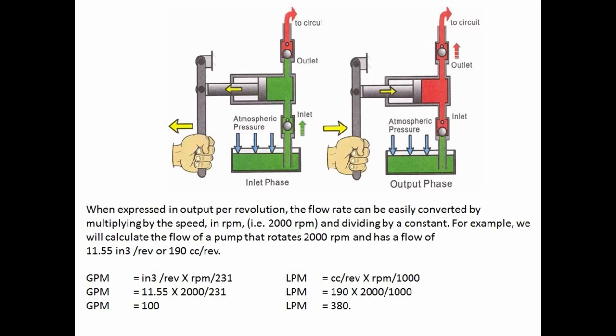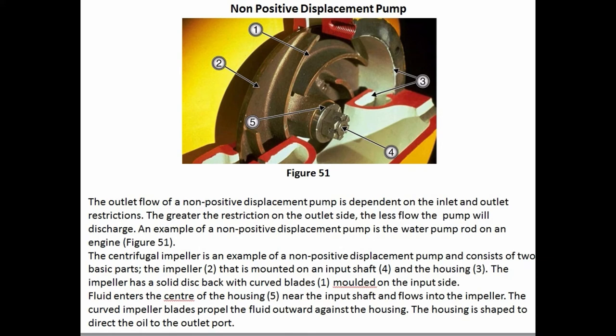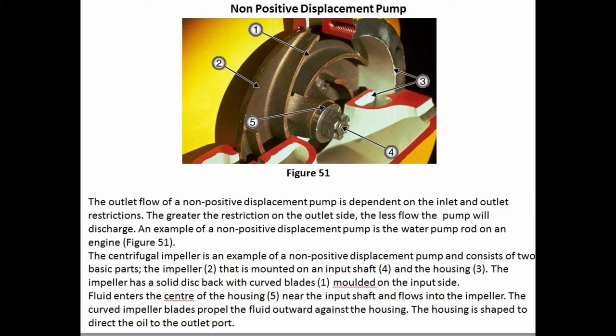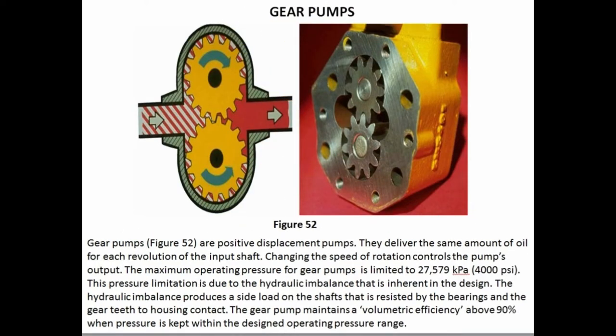The outlet flow of a non-positive displacement pump is dependent on inlet and outlet restrictions — the greater the restriction on the outlet side, the less flow the pump will discharge. An example of a non-positive displacement pump is the water pump on an engine. Figure 51 shows the centrifugal impeller, which consists of two basic parts: the impeller mounted on an input shaft, and the housing. The impeller has a solid disk back with curved blades. Fluid enters the center of the housing near the input shaft, flows into the impeller, and the curved blades propel the fluid outward against the housing, which directs the oil to the outlet.